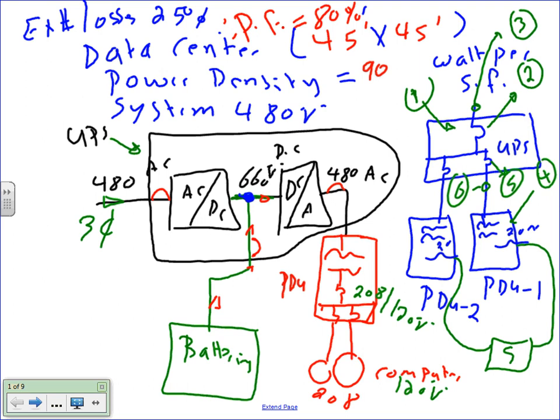So somewhere in the DC level here, it will be charging your batteries at all times. Okay. So what do we need to do? We did this one before, guys. Number one, I need to size the UPS. Number two, the overcurrent protection device for the UPS. Number three is the feeder for the UPS. Number four is a PDU. Number five is the overcurrent protection device for the PDU. And number six is the feeder that's going to the PDU.